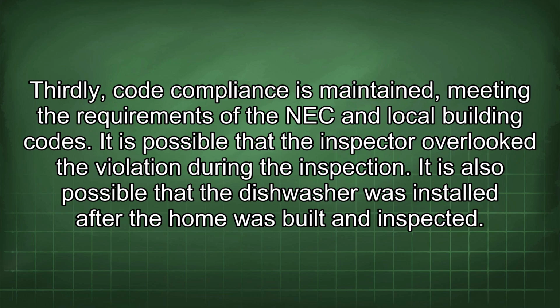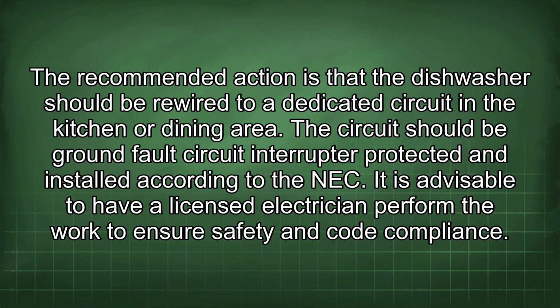It is possible that the inspector overlooked the violation during the inspection. It is also possible that the dishwasher was installed after the home was built and inspected. The recommended action is that the dishwasher should be rewired to a dedicated circuit in the kitchen or dining area. The circuit should be ground fault circuit interrupter protected, and installed according to the NEC. It is advisable to have a licensed electrician perform the work to ensure safety and code compliance.